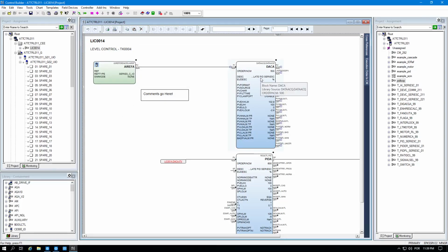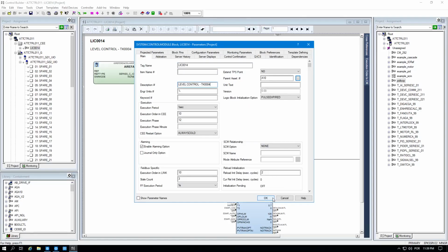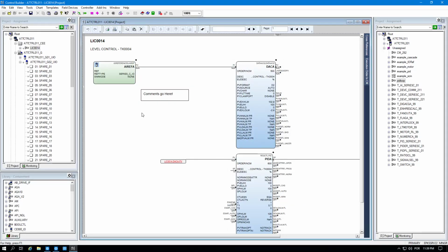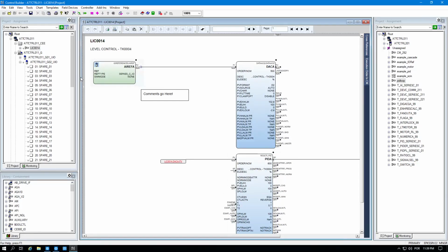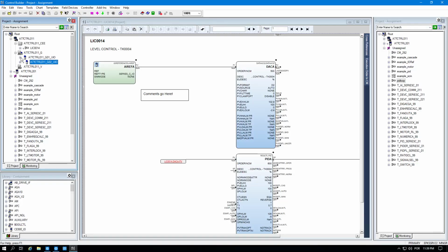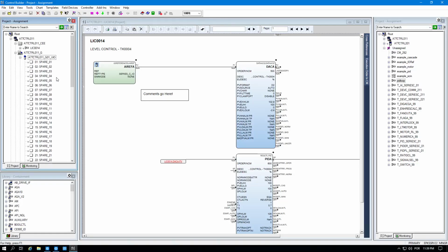Take this description and associate it with the DACA description, associated with the PID description and associated with the CM description itself. Let's save. Next step, we won't make any changes of ranges in these controls or in the PID data. The next step is to define which inputs, which channels they will be associated with from the universal IO modules.